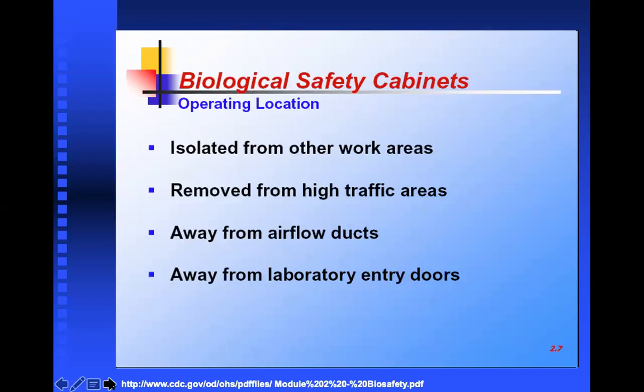The operating location should be isolated from other work areas, removed from high traffic areas, away from airflow ducts, away from laboratory entry doors. That means when you set up a biological safety cabinet, you must remember these four principles. Because if you are working in a biological safety cabinet and suddenly someone opens the door, airflow can enter the cabinet like a big wave and contaminate the materials that you are using. This is why a clean air room should be maintained, and the biological safety cabinet room is specially separated from the other research lab so that you can maintain the airflow and avoid contamination from others.